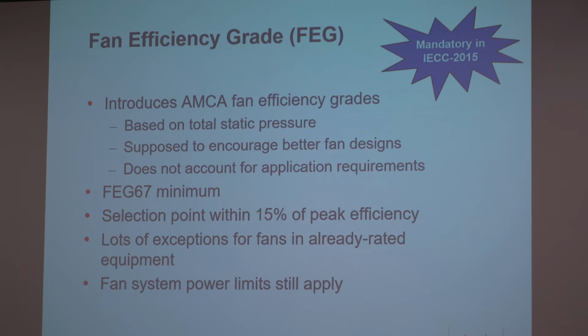But I will point out, it had been assumed, and I'm not sure where we fell on this, that where the fan is already included in the efficiency of the equipment, some people say that's not a system that falls under this category, the system fan power limits. Some people do. There's a little bit of an argument going on about what counts, but I think we finally did settle that packaged equipment does still have to meet the system fan power limits.